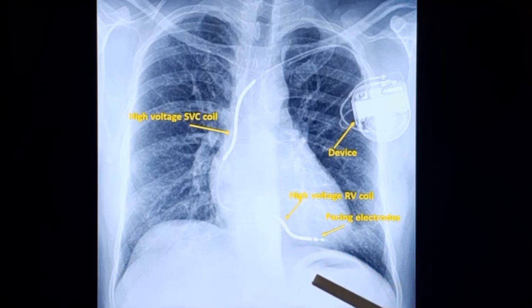In addition to this, ICDs always have facility for backup pacing. You can see two electrodes here, the proximal electrode and the distal electrode. In addition, you can see the spring here. The spring-like structure is a screw which is used to screw the lead into the myocardium. Screw-in lead is shown here. You can carefully watch the spring-like screw over here. That is for anchoring the lead.